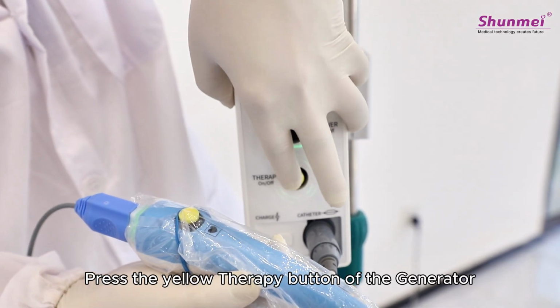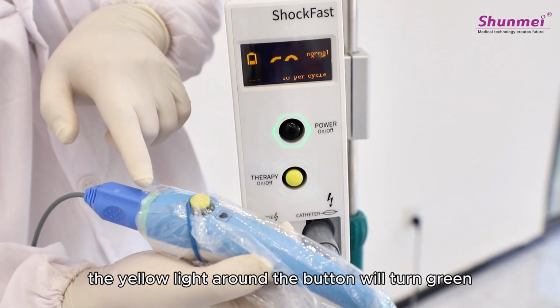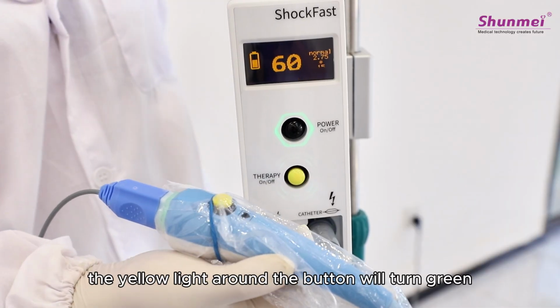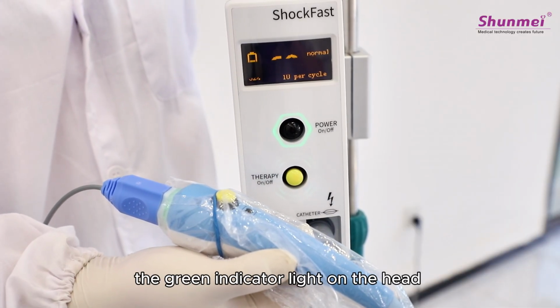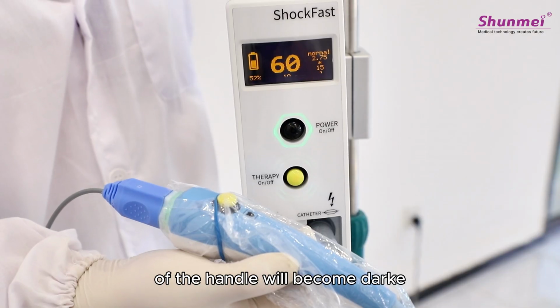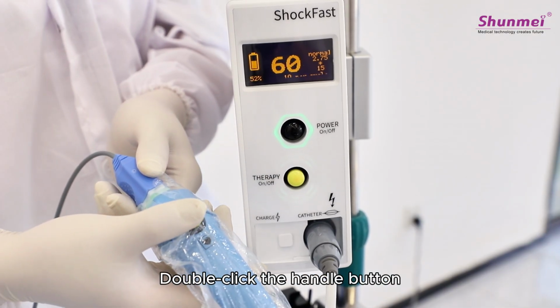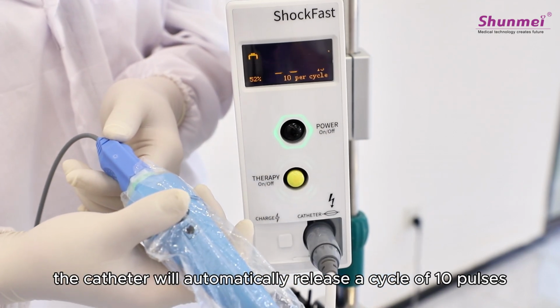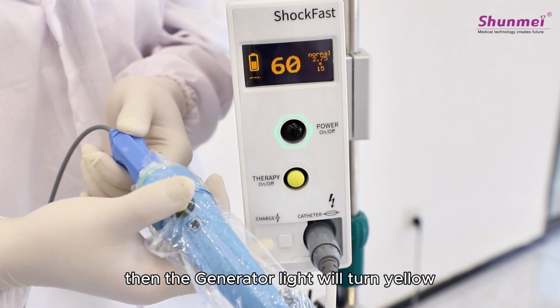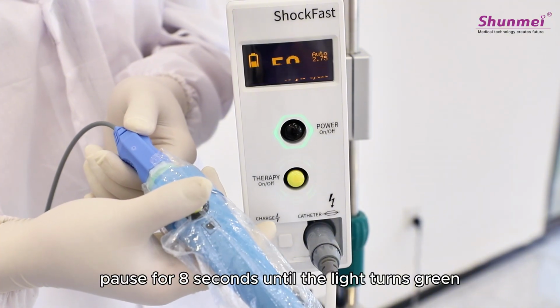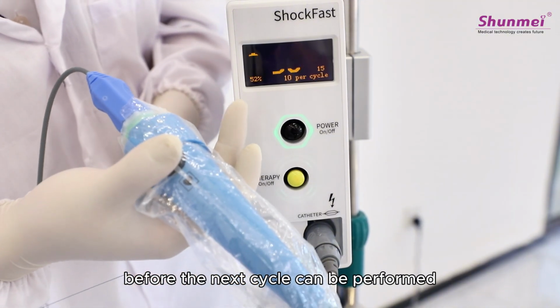Press the yellow therapy button of the generator. The yellow light around the button will turn green, and at the same time, the green indicator light on the head of the handle will become darker. Double-click the handle button. The catheter will automatically release a cycle of 10 pulses, then the generator light will turn yellow. Pause for 8 seconds until the light turns green before the next cycle can be performed.